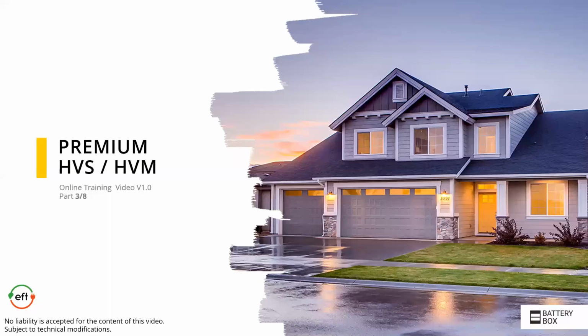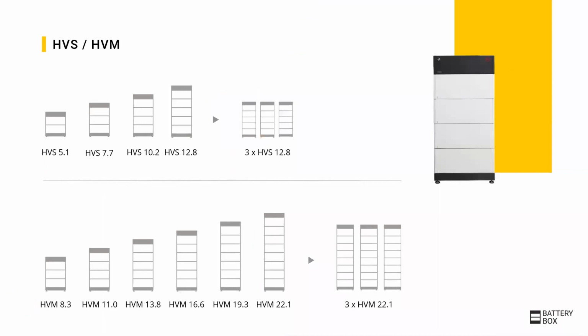After the general support information, we will now look into the product details and start with the premium HVS and HVM. First, a short product overview. The HVS consists of 2 to 5 modules per tower connected in series, whereas each module has about 100 volt. The HVM consists of 3 up to 8 modules per tower, whereas each module has about 50 volt. Up to 3 towers with the same module configuration can be put in parallel.